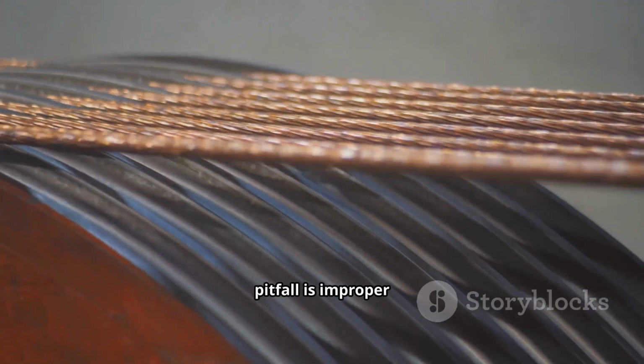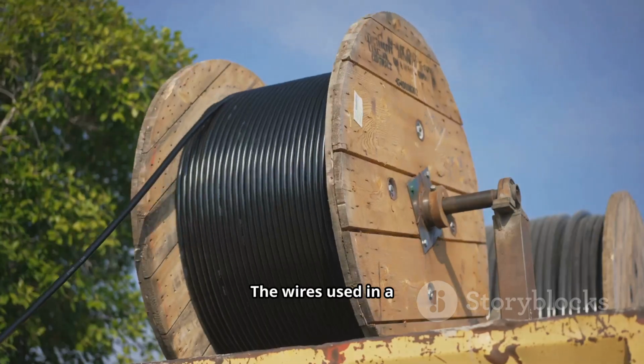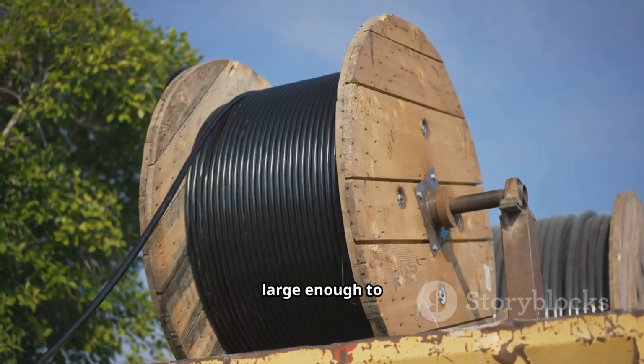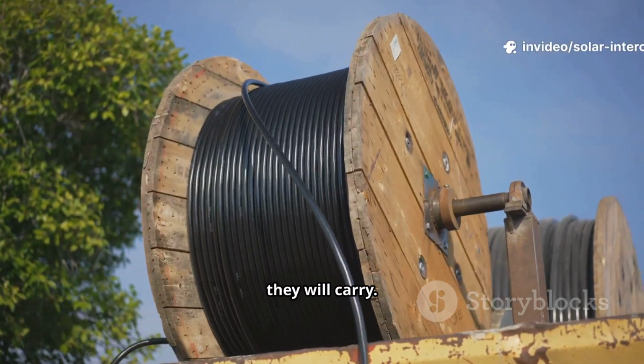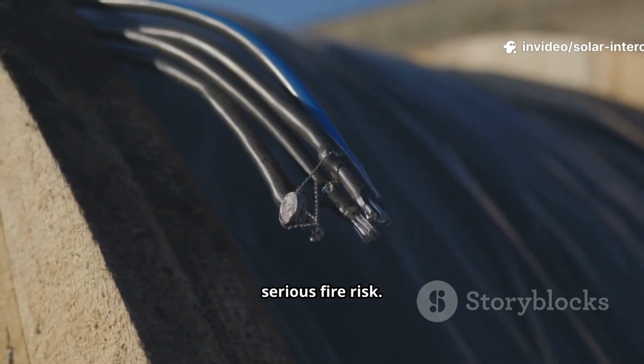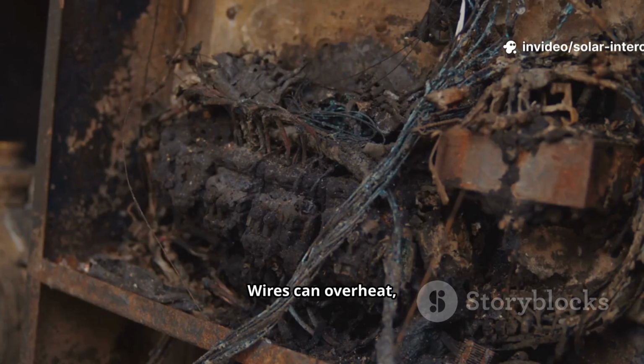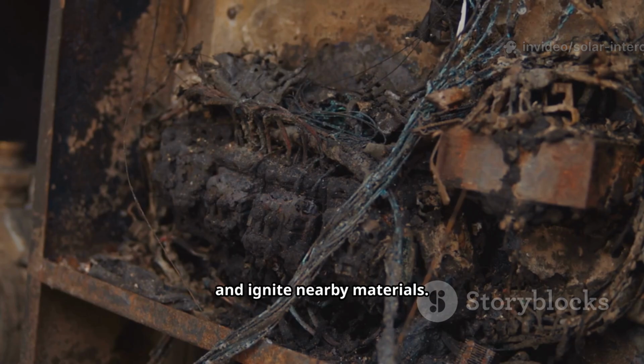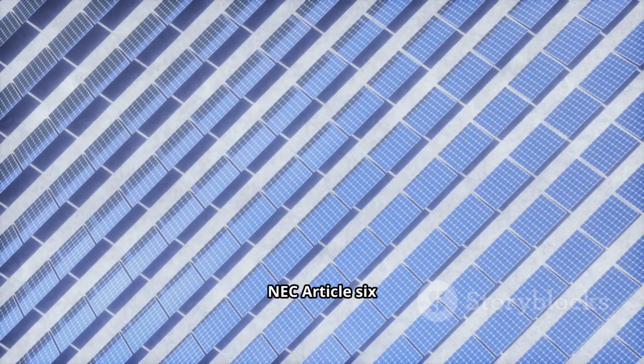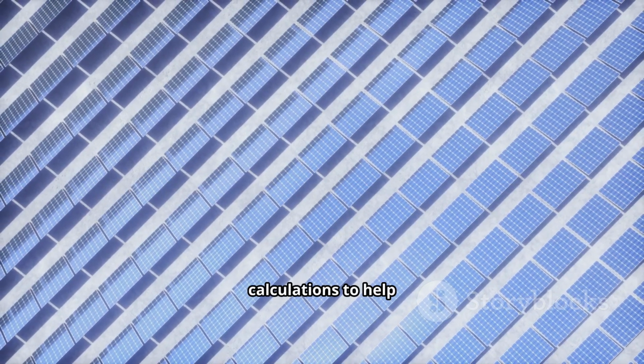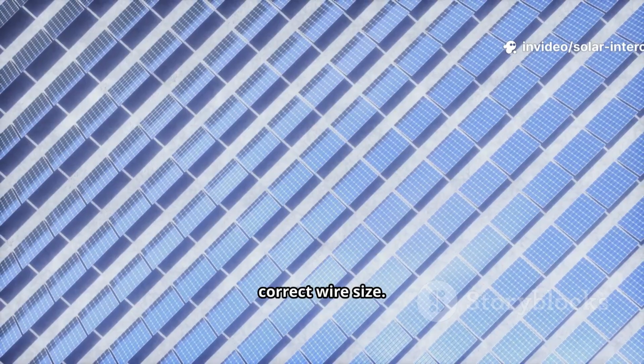Another common pitfall is improper conductor sizing. The wires used in a solar system must be large enough to handle the current they will carry. Using wires that are too small is a serious fire risk. Wires can overheat, melt their insulation, and ignite nearby materials. NEC Article 690 provides tables and calculations to help you select the correct wire size.